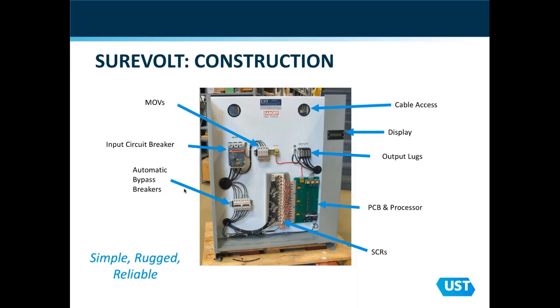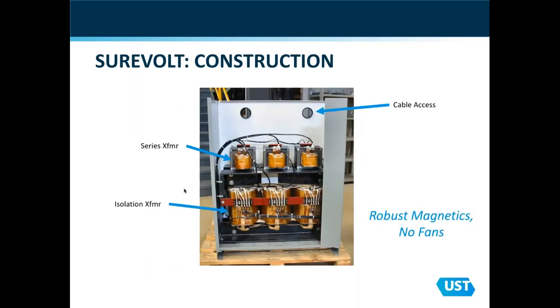Here's a typical example. You can see the simplicity of the design. We have a control board, some SCRs. All units come with an input circuit breaker. We have a set of MOVs for surge suppression. And we also have an automatic fail-safe bypass. We provide a set of output lugs for you to supply your load. And as you can see, very simple, easy to maintain device. If I flip that product around, the rear of the device simply has the magnetics.